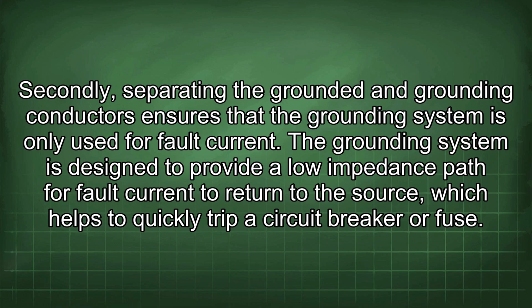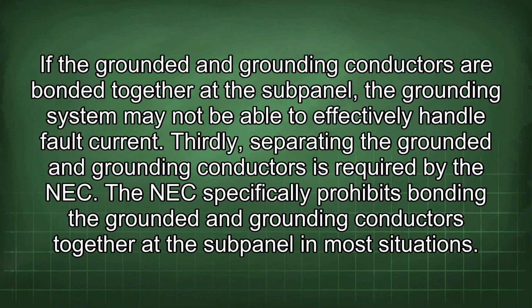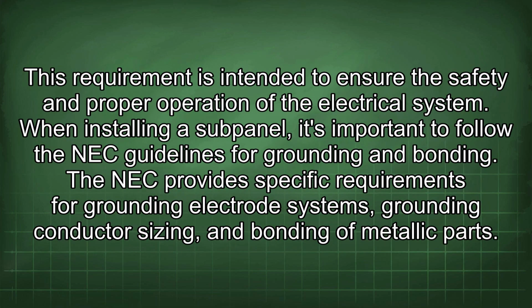Secondly, separating the grounded and grounding conductors ensures that the grounding system is only used for fault current. The grounding system is designed to provide a low impedance path for fault current to return to the source, which helps to quickly trip a circuit breaker or fuse. If the grounded and grounding conductors are bonded together at the subpanel, the grounding system may not be able to effectively handle fault current. Thirdly, separating the grounded and grounding conductors is required by the NEC. The NEC specifically prohibits bonding the grounded and grounding conductors together at the subpanel in most situations. This requirement is intended to ensure the safety and proper operation of the electrical system.